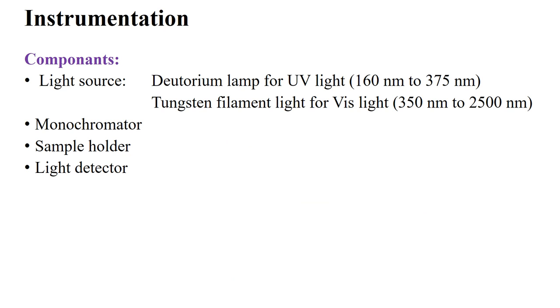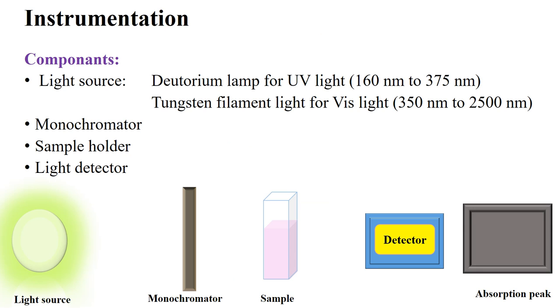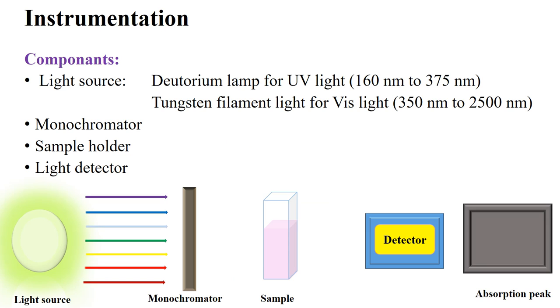For the instrumentation of UV spectrophotometry: you need a UV light source — a deuterium lamp is used for UV light and a tungsten filament lamp for visible light. A monochromator filters the radiation so that only a single specific wavelength passes through, removing all other wavelengths. You also need a sample holder to place the cuvette containing the sample.